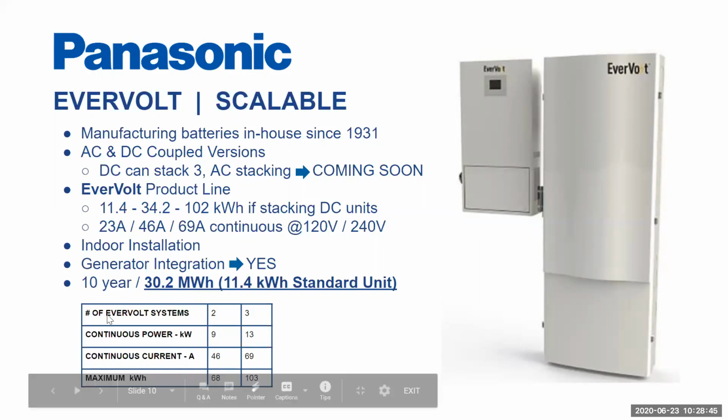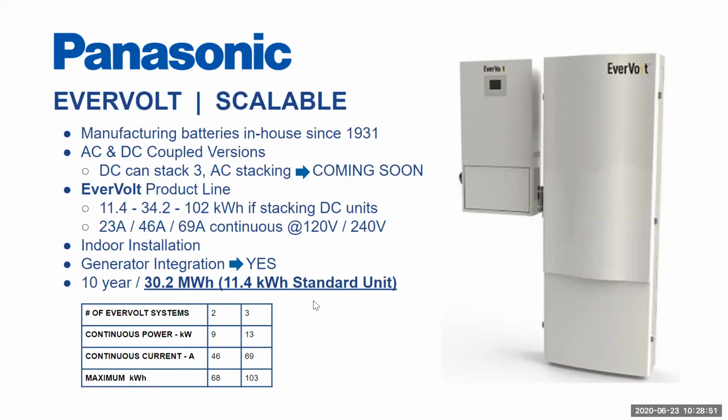And then here, I just took this little snippet from one of their data sheets. But if we have 2 stacked, that's 9 kilowatts or 46 amps of output with 68 kilowatt hours. And then with 3, that's 13 kilowatts of output, 69 amps of current, and 103 kilowatt hours, or 102 and change. So lots of power, lots of energy capabilities when we stack the DC Evervolt system. It's not the cheapest solution per se, but it's very powerful. If you have someone that knows they want a lot of power, absolutely think about DC coupling at Panasonic.